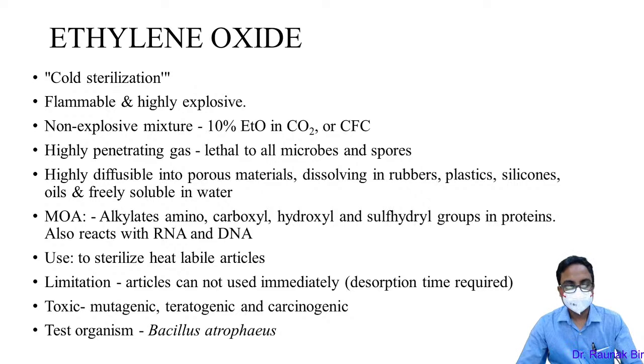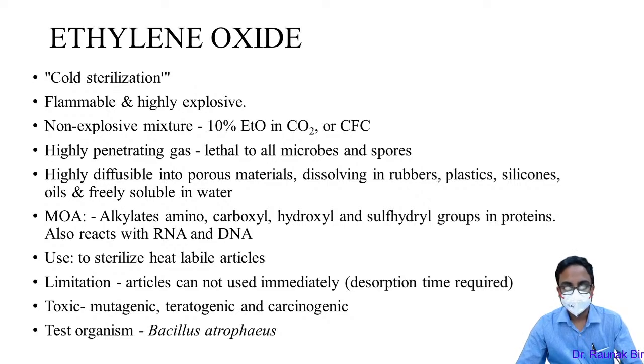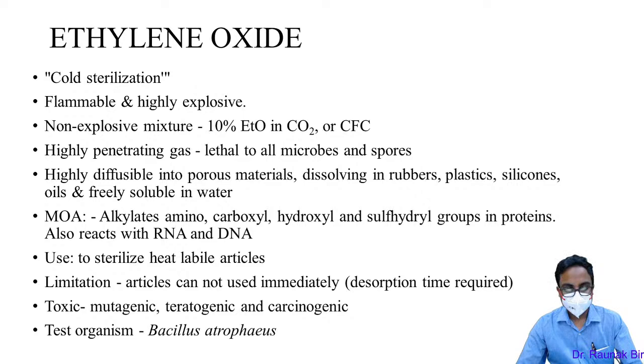Ethylene oxide is used mostly for heat-labile articles. Limitation: articles cannot be used immediately due to a desorption time — the ethylene oxide must dissolve and release out. It is highly mutagenic, teratogenic, and carcinogenic, so its use has decreased. The test organism for biological indicator is Bacillus atrophaeus.